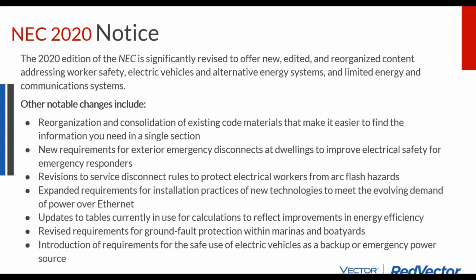This is not necessarily the same main disconnect switch as would be on a power system. This is an additional switch that goes outside the building. It might be your main disconnect switch if everything's already outside the building, or it might just be an additional disconnect switch that goes out of the building and then back into the building to where the equipment is. And so this code used to be mandated by local jurisdictions, and then the solar industry pushed back and said, actually, the main disconnect switch inside the building right next to the service panel is good enough, and we don't want this additional hazard and cost.